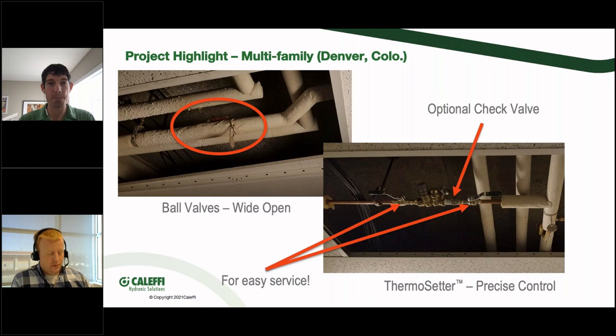I think a great way to look at balancing valves and ball valves is that ball valves typically have what is referred to as a quick opening characteristic. I talked about that before with the curve on the sizing chart for the pressure dependent type balancing valves: when you go from 0% open to 10% open, that's 30% or 40% of the flow. Trying to do that with a ball valve is kind of like when I was doing refrigeration, you'd feel the suction line and be like, oh, that's beer can cold, perfect, you're good there. And that's no way to do it. And not only that, any maintenance guy with a couple of brain cells between his ears is going to look at that ball valve that's about 7/8 closed and go, that ain't right.